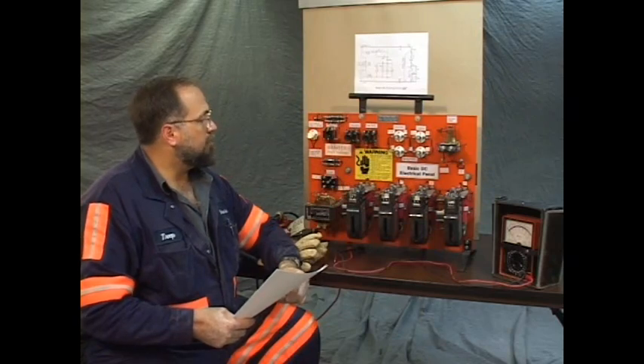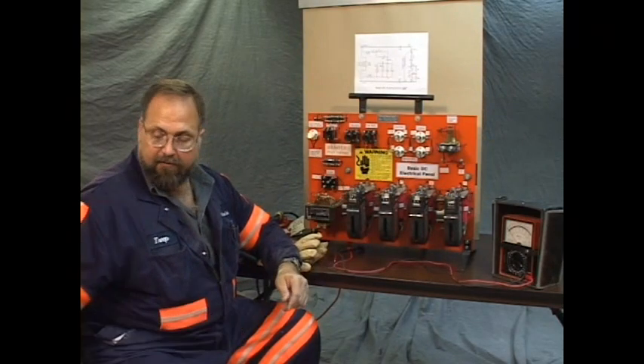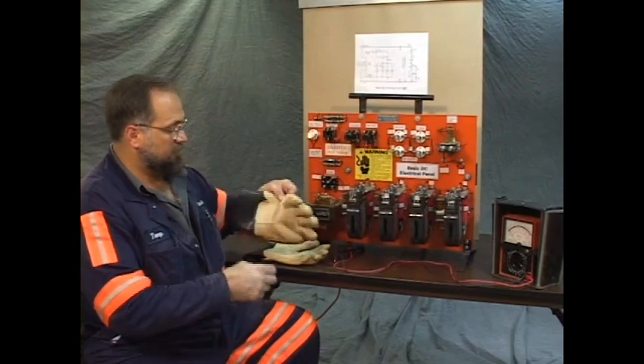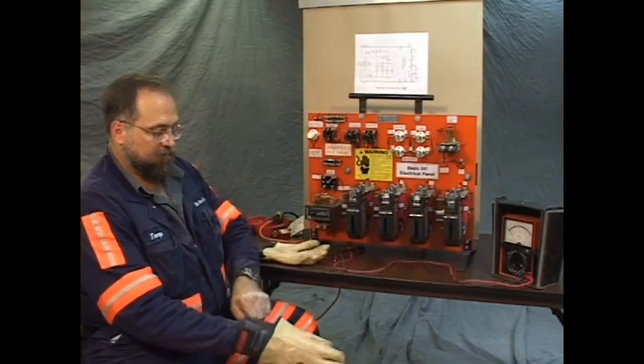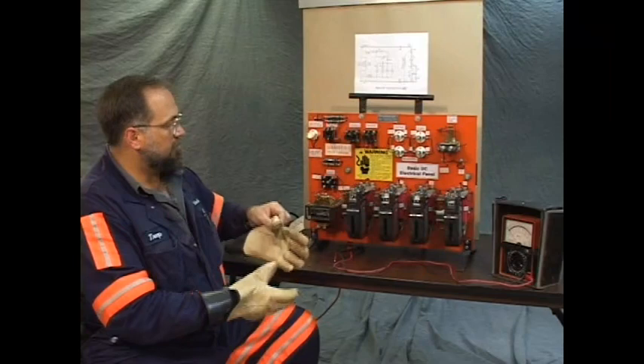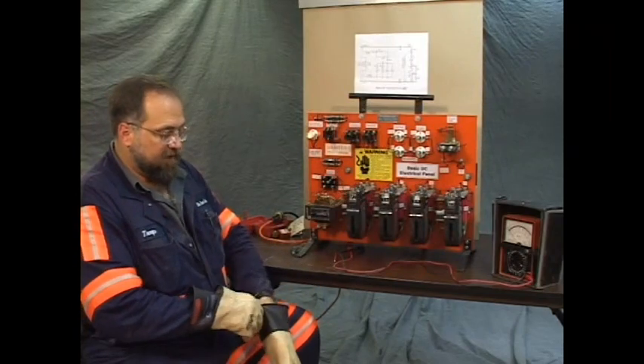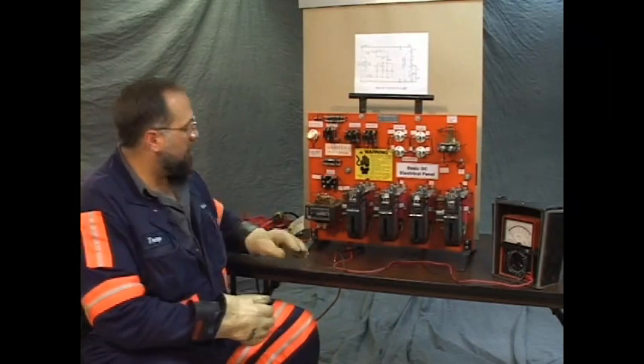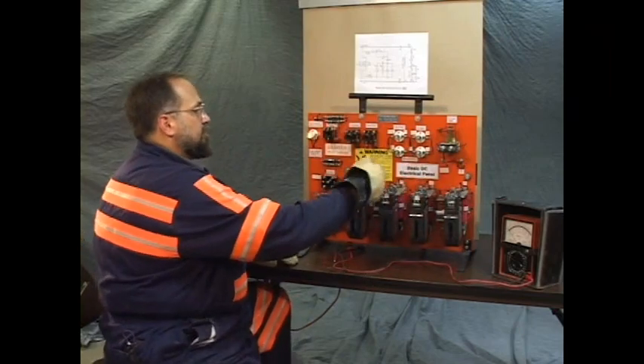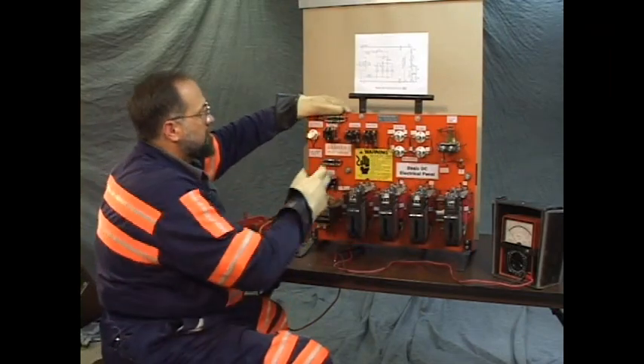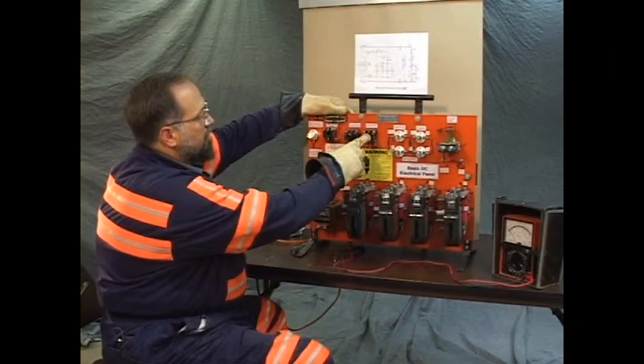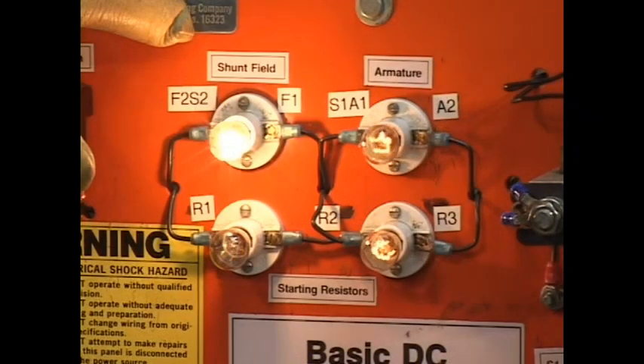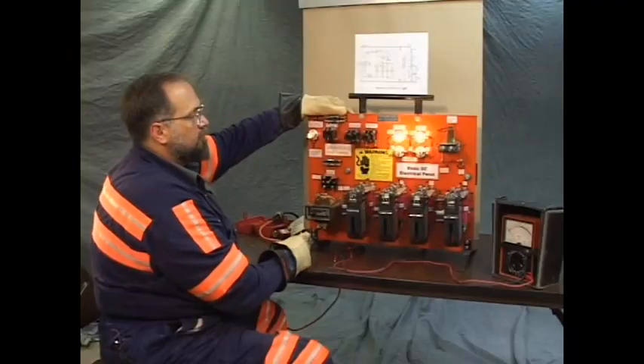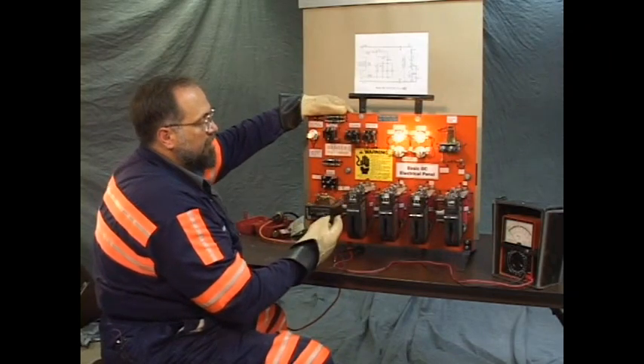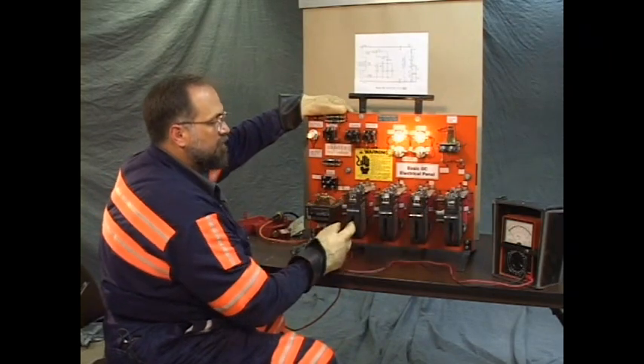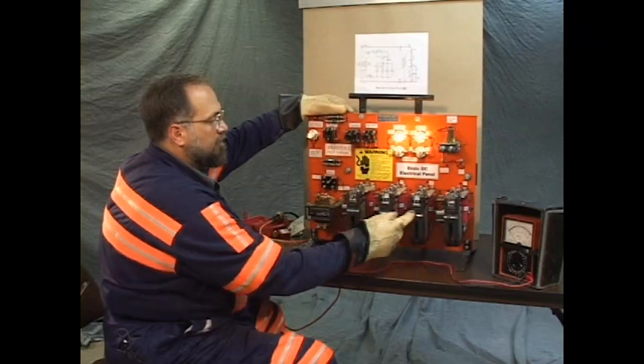Well, we'll begin by showing you normal operation of the panel, then we'll install the problem. I'm going to put the gloves on. These testing panels, like panels underground, have a lot of exposed conductors. Much of this surface here is energized at all times. It powers on the panel. Good practice to have the gloves on. That's normal operation. You note 3 clicks: M1 and M2 go in simultaneously, then 1A, and then 2A.